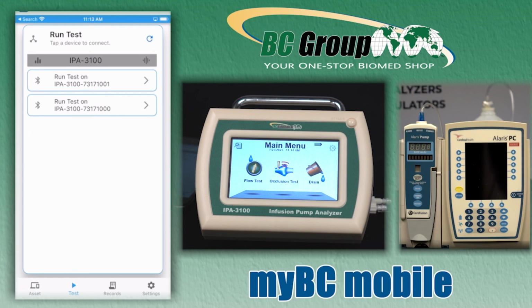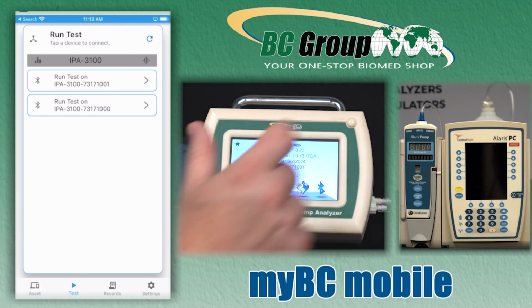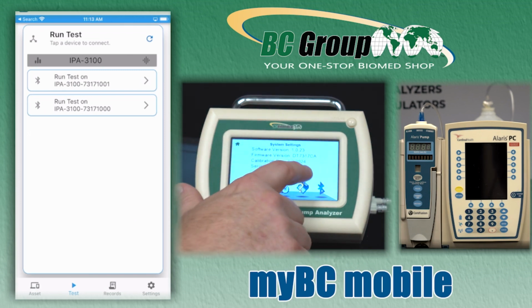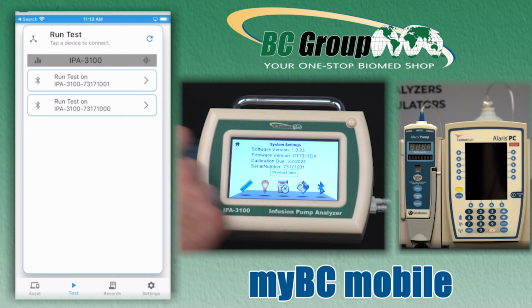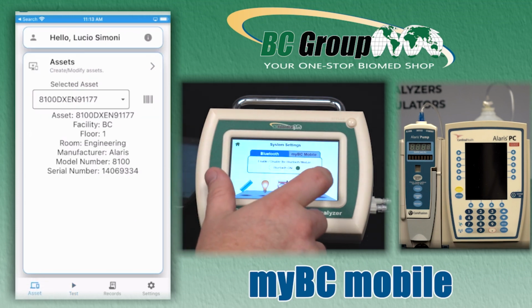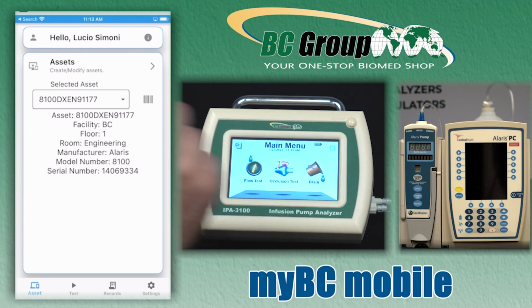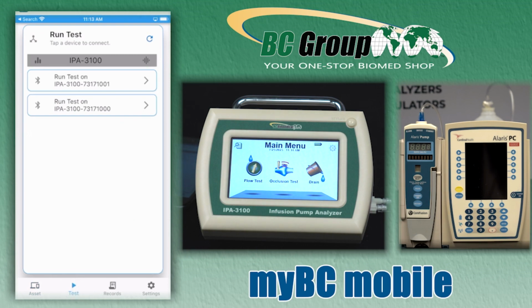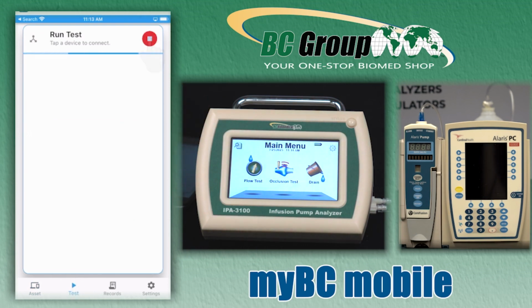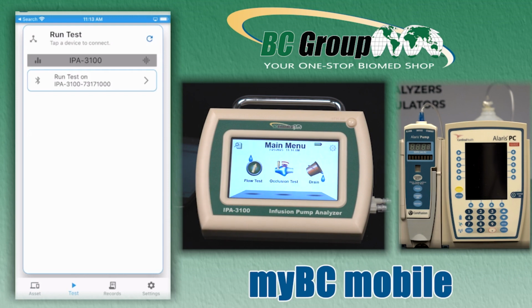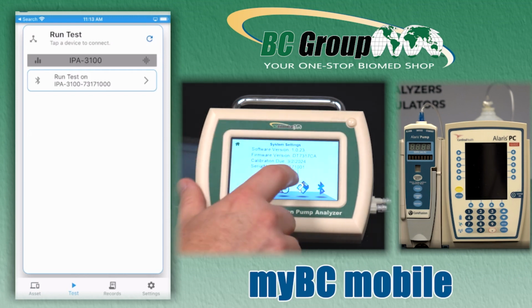Now I'm prompted with what equipment I want to use. So we're going to select the IPA 3100. And right now we have two displayed because there are two close by that it can find using Bluetooth. So I'll go into my settings and confirm that this is serial number 1001. And now we can see that unit on myBC Mobile. I'm going to go back to the asset, and if Bluetooth is turned off, so what happens there? Then we can go through and start our test, and we can do a refresh, and now it shouldn't find that unit anymore. So now we can say, what unit do I have?